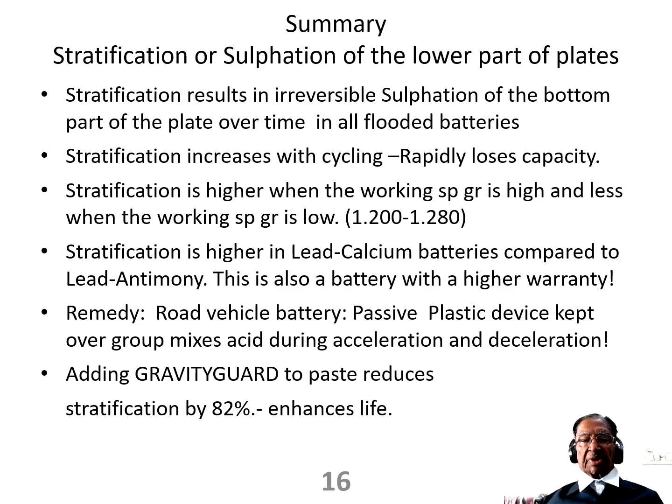Summary: stratification, or sulphation of the lower part of the plates. Stratification results in irreversible sulphation of the bottom part of the plate over time in all flooded batteries. Stratification increases with cycling, and the battery rapidly loses capacity. You must remember that. Even the domestic inverter battery is used in this manner. It is cycled very often, probably every day, or a few times a week.